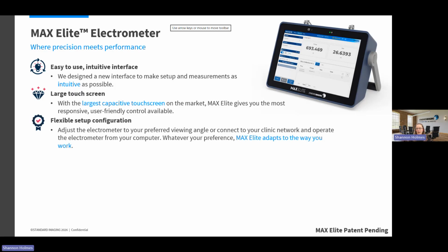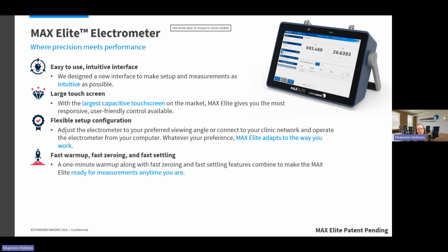We have a carry handle for the electrometer that doubles as a stand, so it's got several different positions. If you're standing above it, it can be flatter on the table. If you're sitting down or it's more at head height, you can tip it up higher so that you can see and access that screen as easily as possible. We also allow you to operate the unit remotely from your computer, and it'll mirror the screen there. So if that's the easier way to do it for you, you can certainly operate it that way as well.